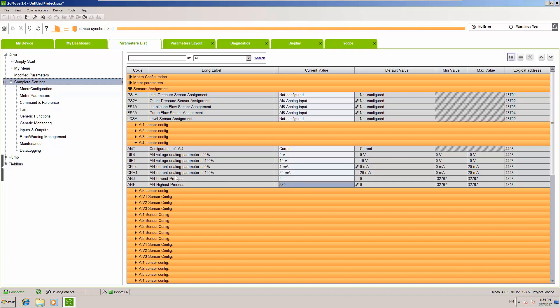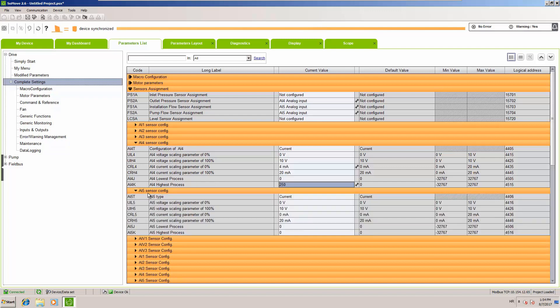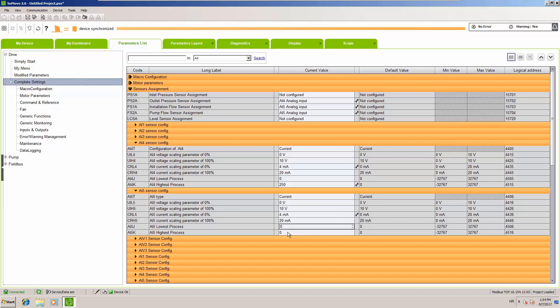The same must be applied for our flow meter: 4 to 20 mA, and a range of 0 to 200 to represent 0 to 20 cubic meters per hour. This means the drive will have correct values when reading our sensors.